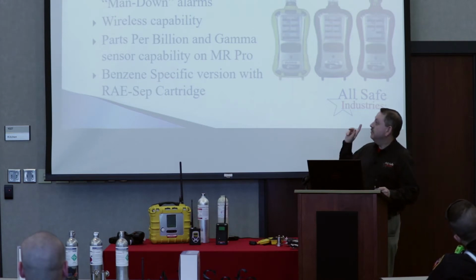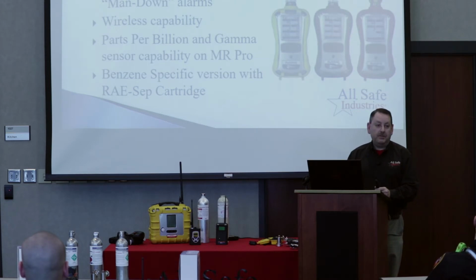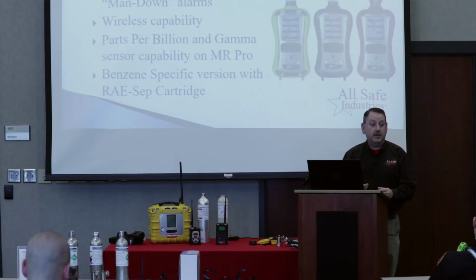And then the one on the end, the red one with the cartridge attached, that's actually the MultiRAE Benzene. What's cool about the MultiRAE Benzene is you can attach a separation cartridge. Remember how I said when you're taking a reading that it will measure all VOCs at the same time. It won't tell you what color the piece of paper is. It'll just give you the reading of what the gases are. With that MultiRAE Benzene, it scrubs out all the background VOCs and only allows the benzene to come through so that you can get a direct benzene reading. This is useful at petrochemical facilities. Okay? So that's the whole MultiRAE family. And again, that one's wireless, and the ones that you guys are buying are wireless also.